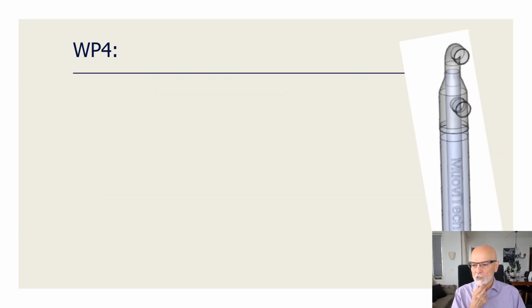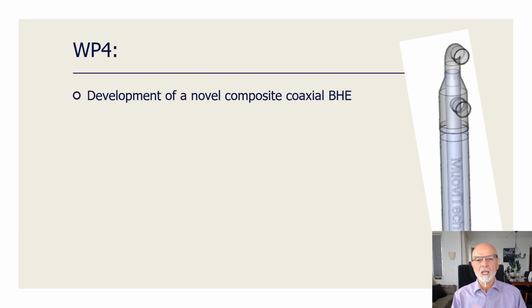Work package 4, focusing on the installation of the borehole heat exchanger, brings innovative design based on a composite coaxial borehole heat exchanger. As mentioned, it will have stronger mechanical strength with a thin-walled external pipe, and a thicker inner wall for the turbulator installations.